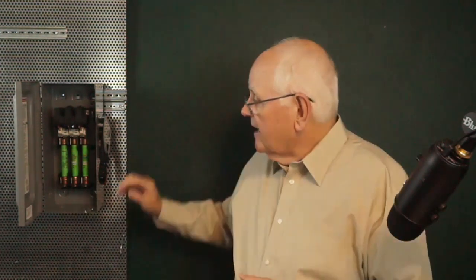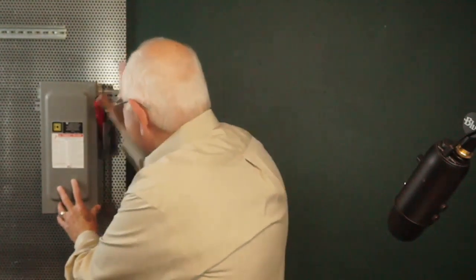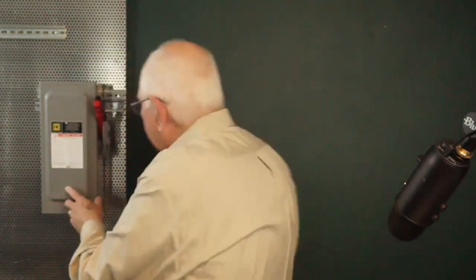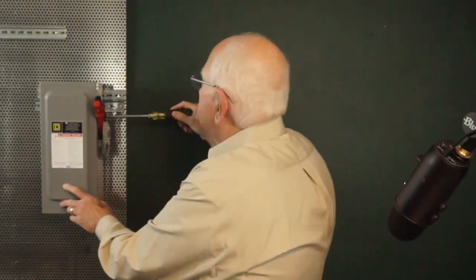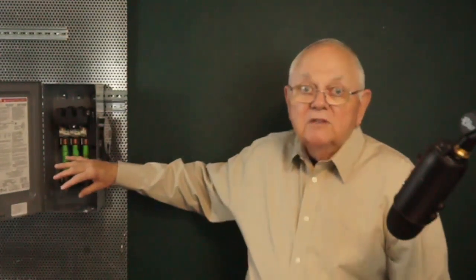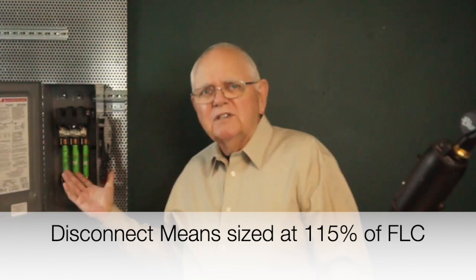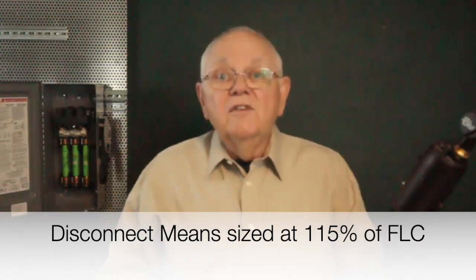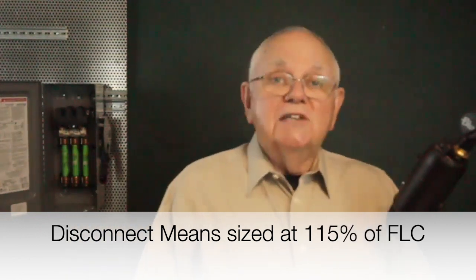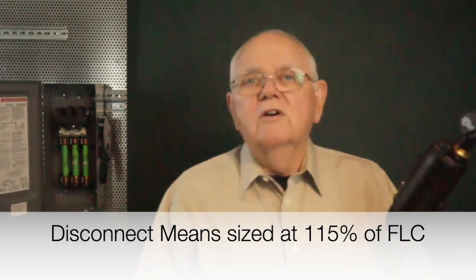Now, no matter what the position, we'll close the door, we'll throw the handle to the up position. We now have power to our industrial machine. I can obviously throw the handle and open the disconnect, or if the handle's in the up position, I can go ahead and override the interlock, open the door, and even with the door open, let's say I'm doing some troubleshooting and something goes wrong, I still have to be able to throw that handle down and shut the power off. So that's a requirement. As far as the sizing of the disconnect for an industrial machine, it's 115% of the sum of the full load currents on the machine. So we size our disconnect at 115% of whatever the full load current is on the machine.